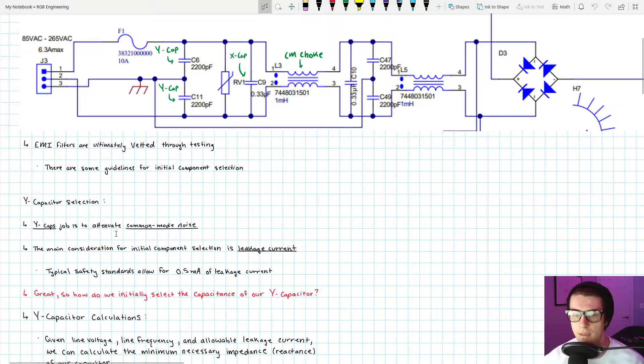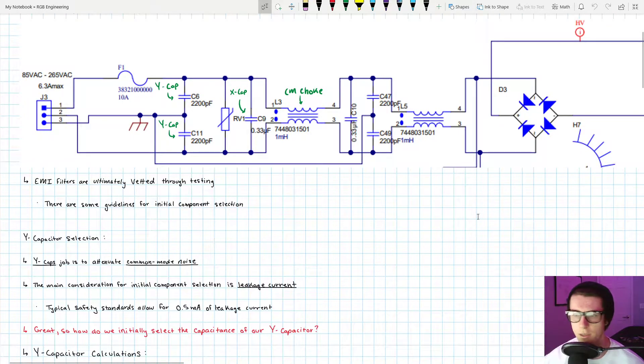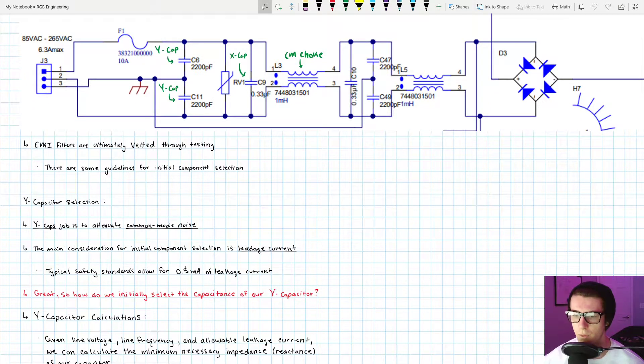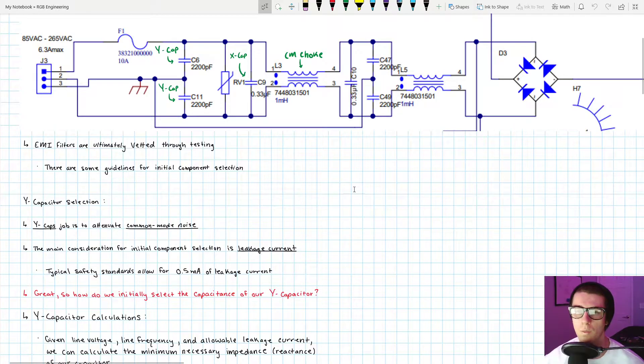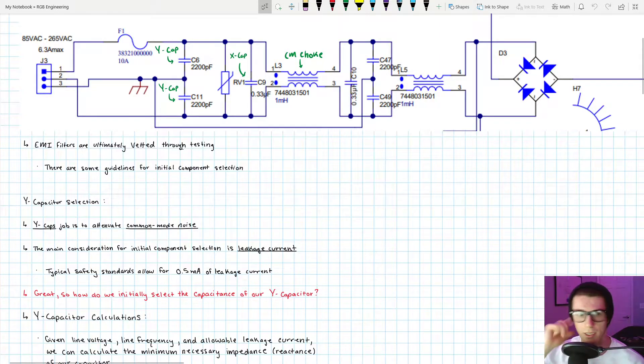First up is Y capacitor selection. The Y cap's job is to attenuate common mode noise. The main consideration for initially choosing a Y capacitor is its leakage current — the amount of current flowing from line and neutral to chassis ground. Since Y caps connect to the safety ground, we don't want the chassis to become live under any circumstances, which is why there are regulatory standards limiting how much leakage current is allowed during normal operation.